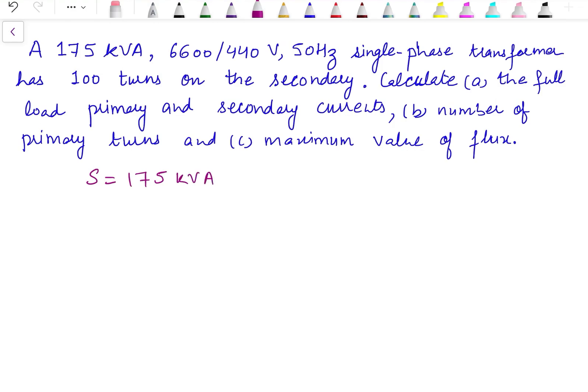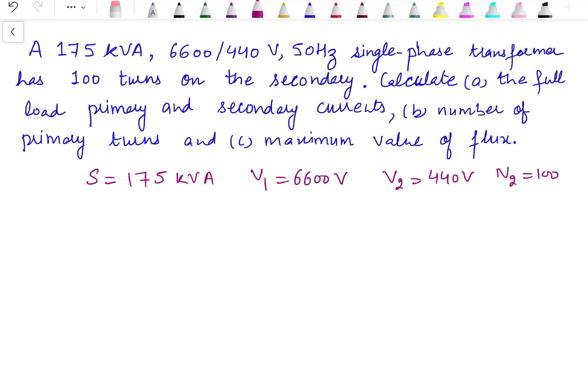Now let's start with the first problem. A 175 kVA, 6600 to 440 volt, 50 Hz single phase transformer has 100 turns on the secondary. Calculate the full load primary and secondary currents, number of primary turns, and maximum flux. The kVA rating is 175 kVA, primary side voltage V1 is 6600 volts, secondary side voltage is 440 volts, and number of turns on the secondary N2 is 100.